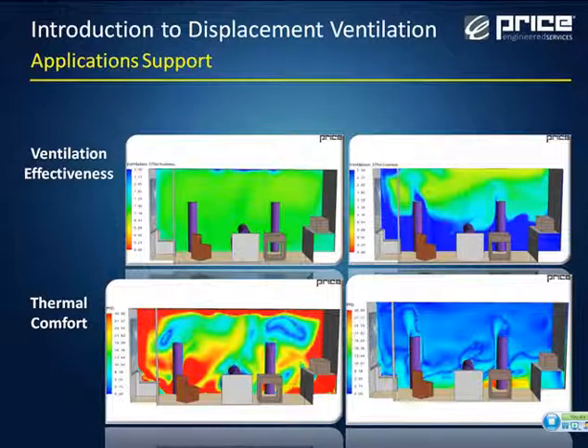On the left, unfortunately my diagram tags aren't showing up, but on the left is the mixed system and on the right is the displacement system. So if we look at the ventilation effectiveness of the mixed system, we see ventilation effectiveness pretty well even across the room. It's around 0.7, 0.8, and again, not really 1, which ASHRAE says it could be. The only region where it's really much higher than 1 is right around the diffuser, obviously, because that's where the fresh air supply is.